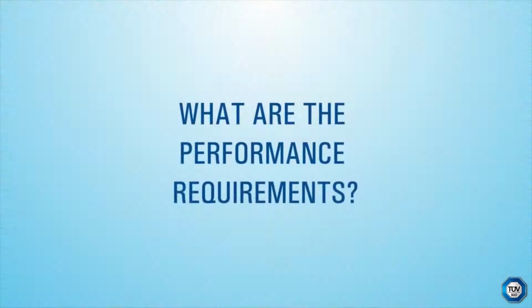The nature of the fluid will directly influence the choice of flow meter, as not all flow meters can be used for all fluids and fluid applications. The range of information that you need includes things like, is it a gas or a liquid that you're dealing with? What pressure conditions, temperature conditions, what's the density of the fluid, the viscosity of the fluid? Is it corrosive? Is it hazardous? So you need to be able to supply all of that information for the fluid.